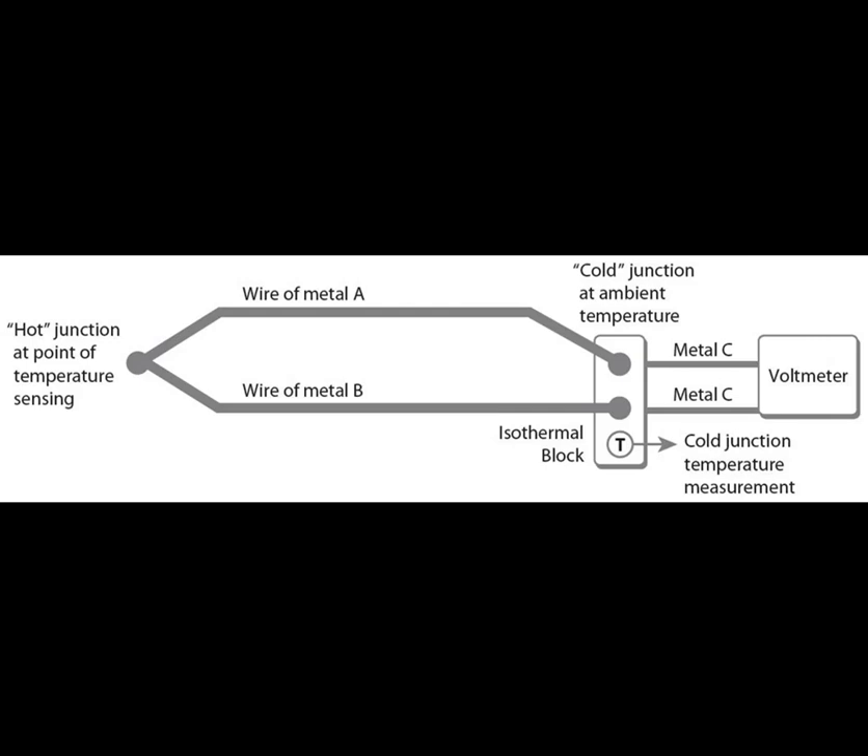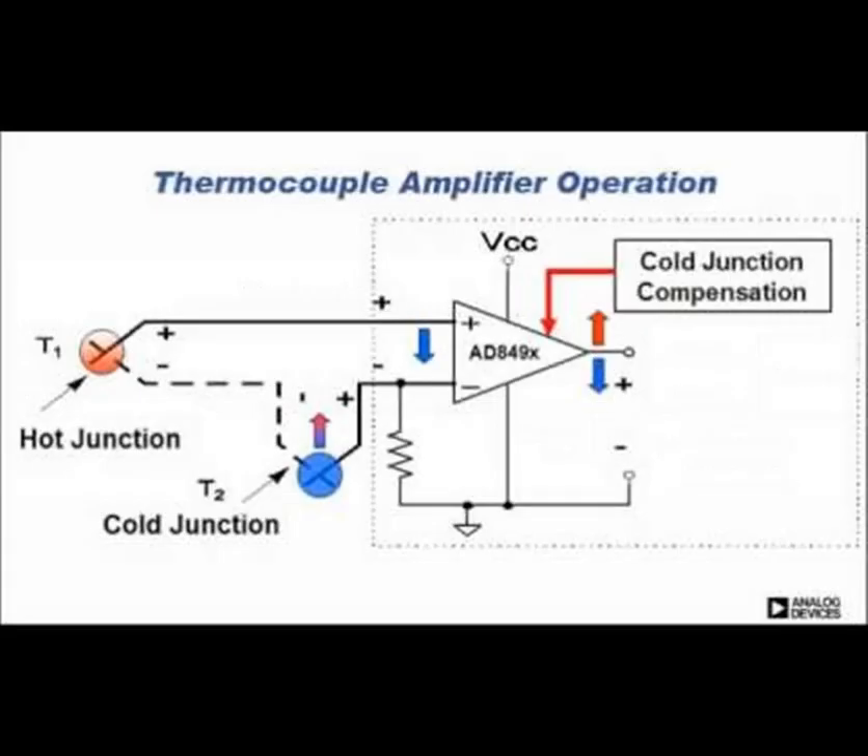The voltage generated by the thermocouple is typically small — on the order of microvolts per degree Celsius. Therefore, signal conditioning is essential. This involves amplification and conversion of the analog signal into a readable temperature value using linearization techniques based on the thermoelectric properties of the chosen metal pair.